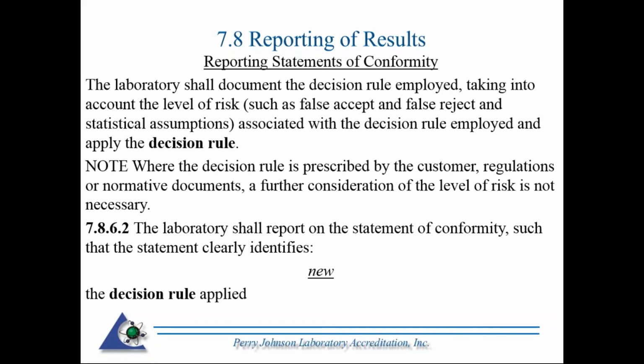So these are for whenever you're making a statement of conformity. If you're not making a statement of conformity, if you're not stating pass, fail, in tolerance, out of tolerance, you're reporting the results and the measurement uncertainty, then there is no decision rule to be considered. However, if you are, and it's always been a requirement that you had to take measurement uncertainty into account, this is just specifying how you are doing it.